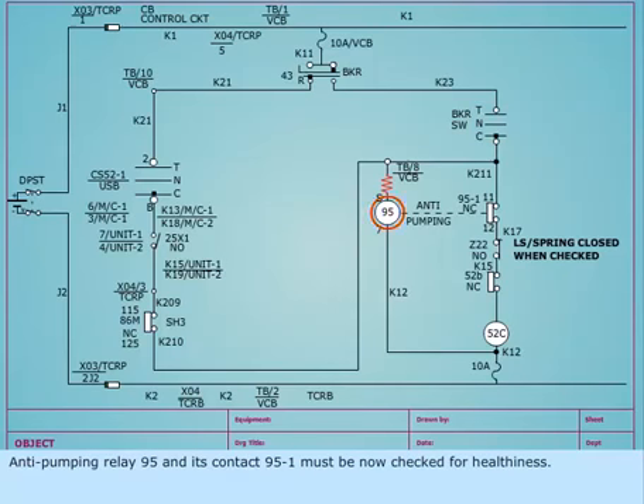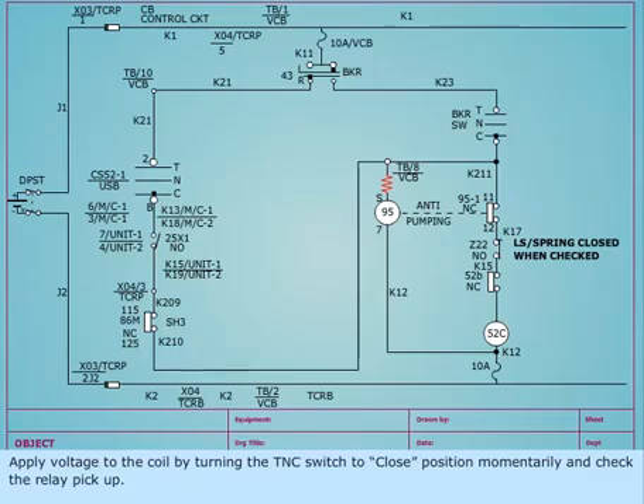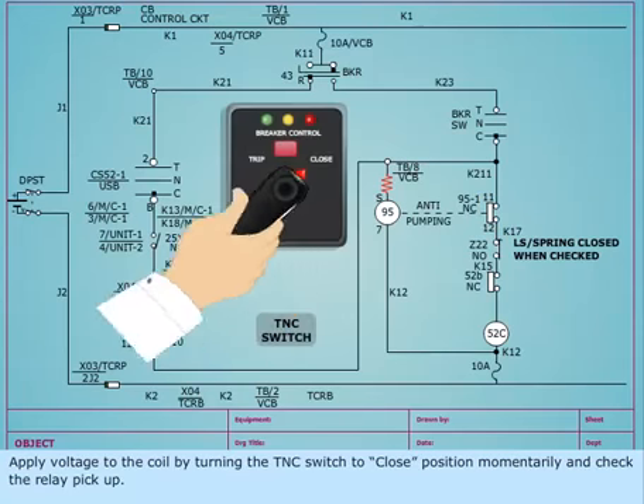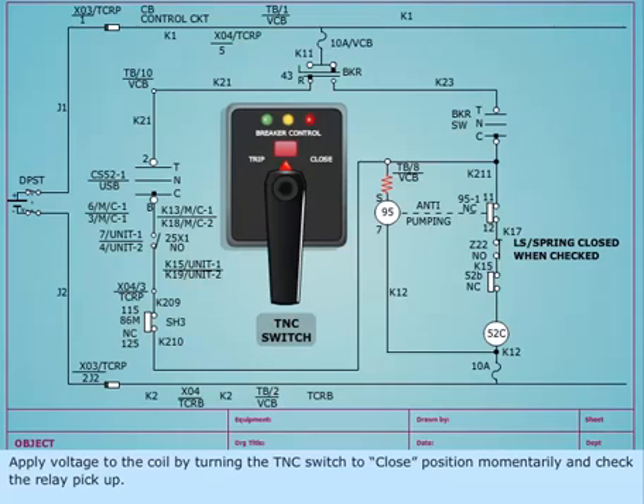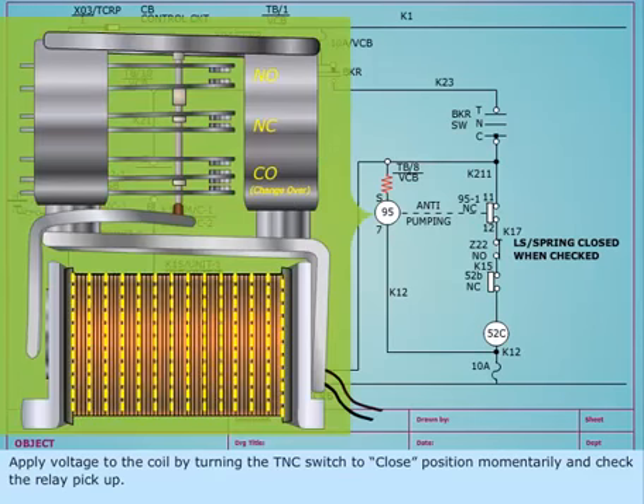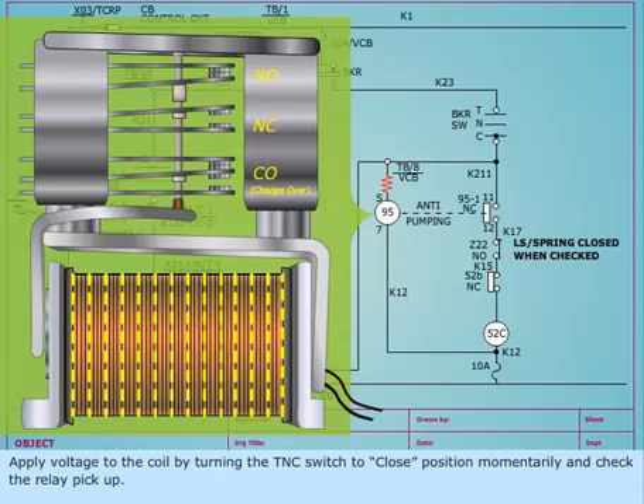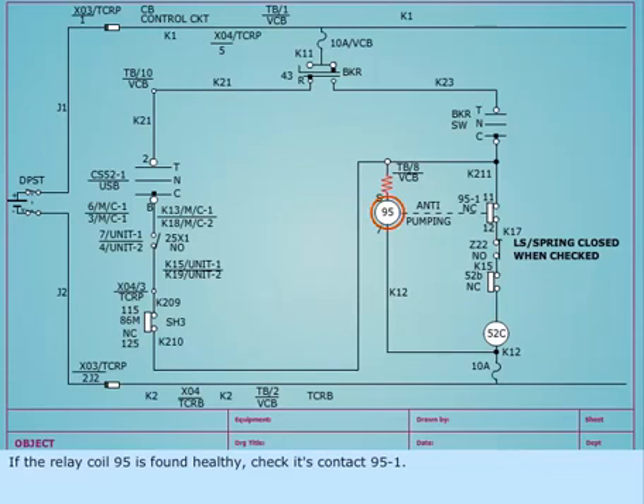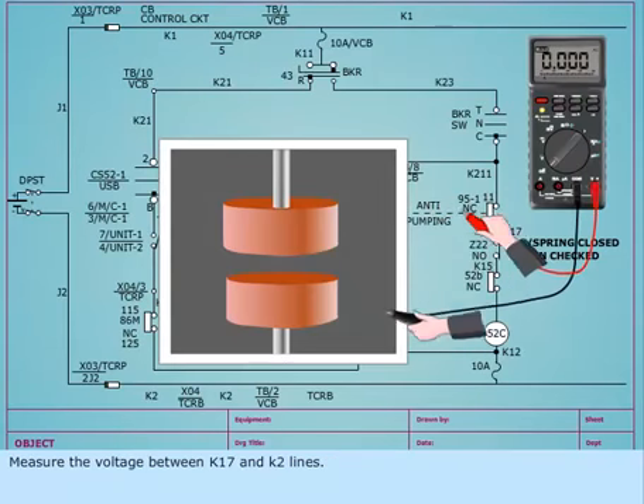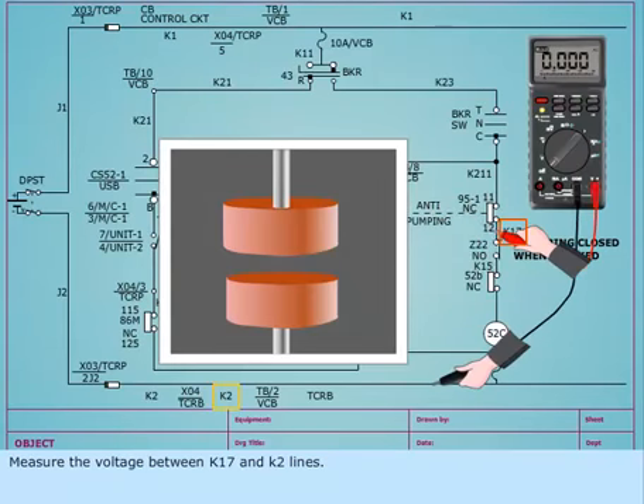Anti-pumping relay 95 and its contact 95-1 must be now checked for healthiness. Apply voltage to the coil by turning the TNC switch to close position momentarily and check the relay pickup. If the relay coil 95 is found healthy, check its contact 95-1. Measure the voltage between K17 and K2 lines.